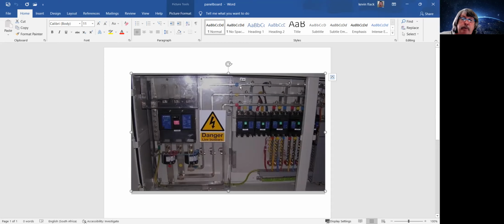I am aware that you do get busbar connected fuses, which are pretty good in the sense that they are protected from their load side going down, and so they are permanently connected to the busbar. That is a solid connection. There's no requirement for loading and mechanical stresses up to the actual fuse itself. So those would effectively work. You would still possibly have to look at making sure that the fuse line down here is supported in such a way that mechanically any short circuit doesn't pull those cables apart and create a problem. As I said, a floating piece of cable within a busbar zone is really where a problem could develop quite specifically.